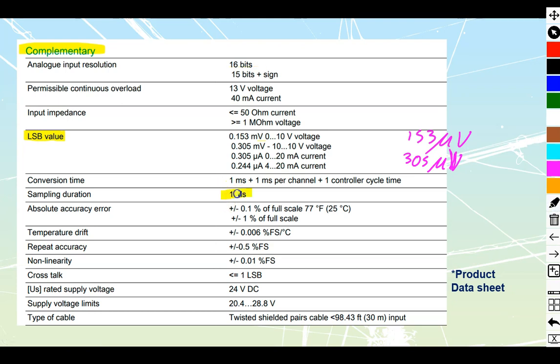The sampling duration is given as one millisecond and conversion time is one millisecond plus one millisecond per channel plus the controller cycle time. In other words, I'm going to have one millisecond of sampling plus, if I've got multiple channels open like two of these channels, it's going to be one per each channel because that's the cycle through plus the controller cycle time. This tells you how rapidly the PLC scan time is updating the data coming in.